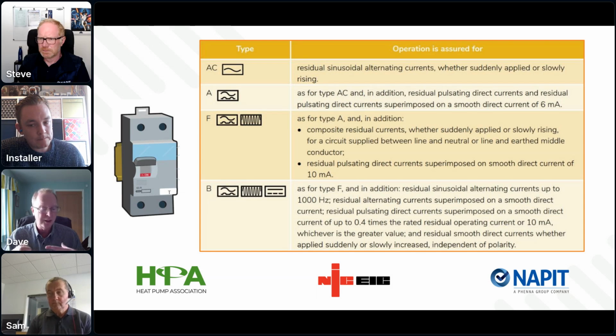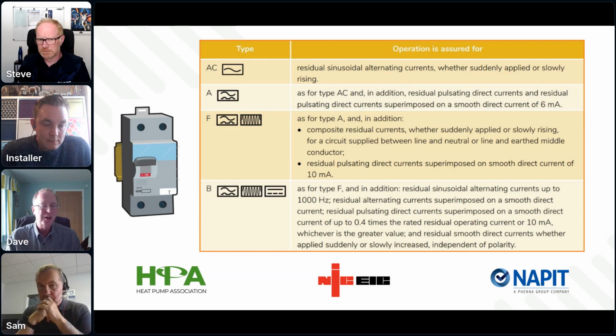The reason for that is the scenario we're talking about is where no other information is there to support our choice. So we're recommending Type B at that point because it protects the broadest range of characteristics available within the set of RCD types that we're talking about. And even in our guidance, we say this does represent the most expensive option out of these types of RCD. But let's put that in context of the price of a heat pump. Four or five times more than the cheapest RCD is still 1% of the cost of a heat pump installation, in a nutshell.